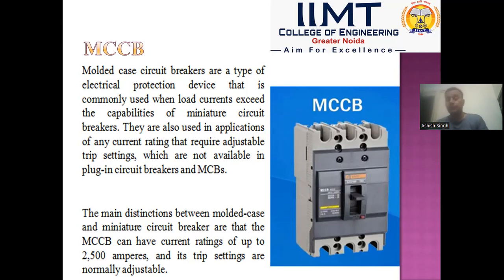That means if we need to adjust the trip current, we prefer to use MCCB instead of MCB, because we do not have any setting for adjusting trip current in case of MCB, whereas in MCCB it is provided. So we are using MCCB, molded case circuit breaker, if we need adjustable trip setting, which is not available in plug-in circuit breakers, or simply MCBs.